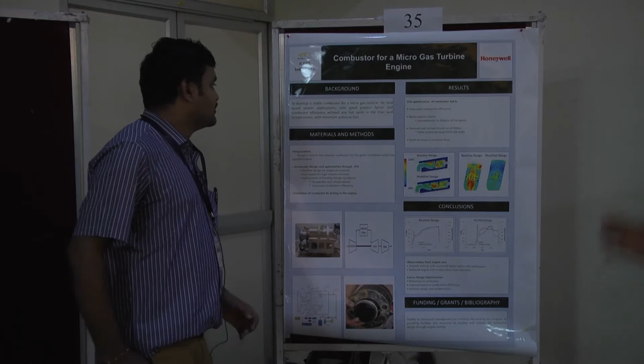Hi. Here the objective is to develop a stable combustor for a micro gas turbine engine. It should have a good pattern factor and good combustion efficiency, and we should not see any hotspots on the combustor liner wall, with minimum pressure loss. So these are the major requirements. We started with empirical calculation, and using an in-house code, we developed the reverse flow annular combustor for the given conditions within the specified layout.